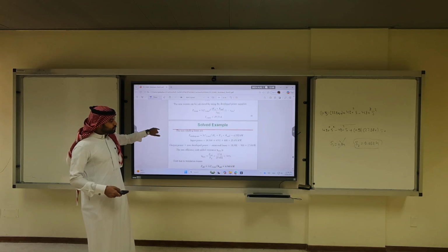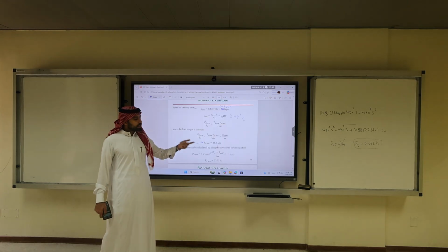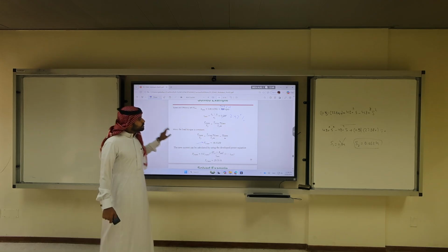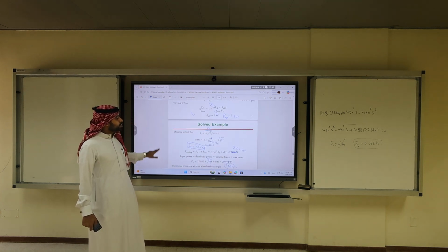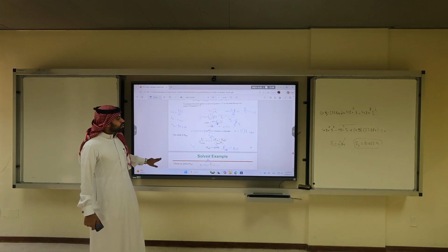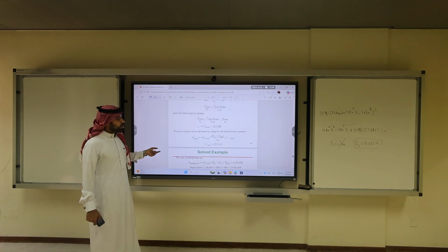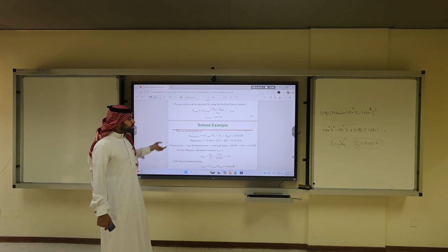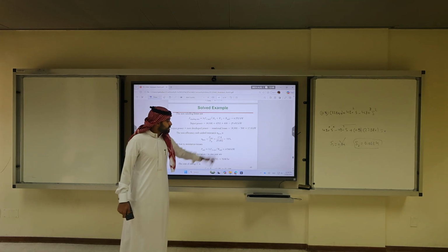We don't have time to do it. But the way he did it is, instead of doing PD, he compared the ratio of PD from old to new. If you reduce it by 20%, your developed power is 18.3 compared to your old developed power of 22.8. Then the new current can be calculated to be 25 amps. You repeat the same calculation, and then you should get efficiency of 70%.